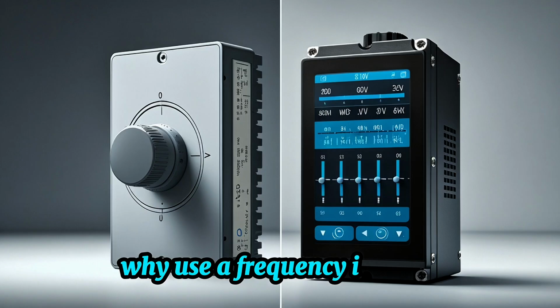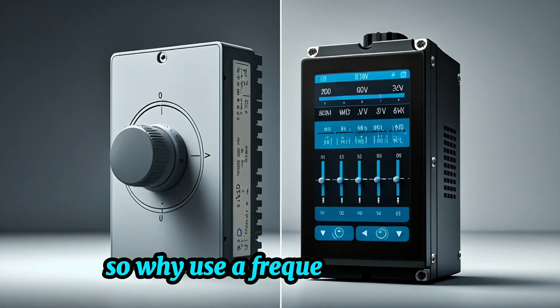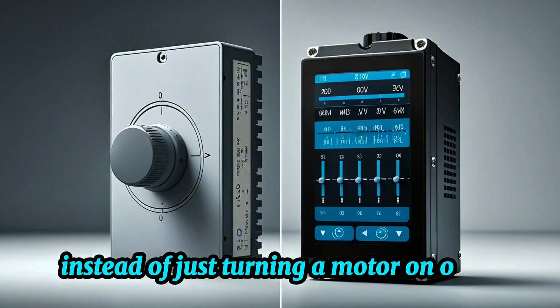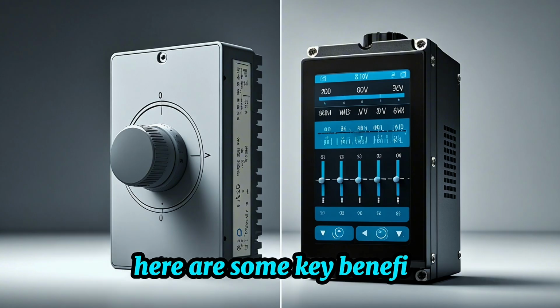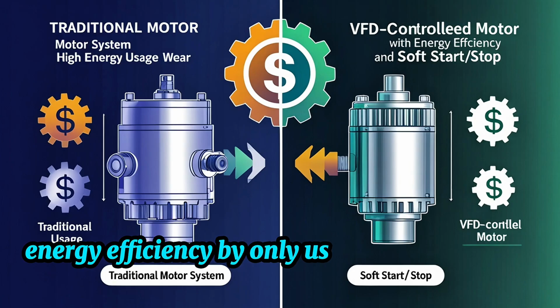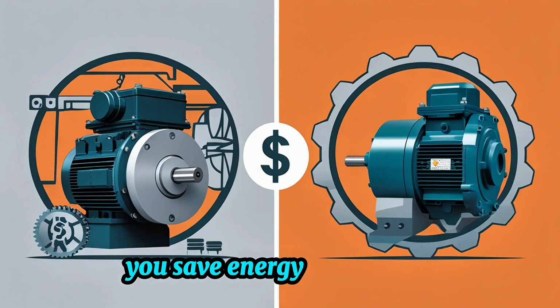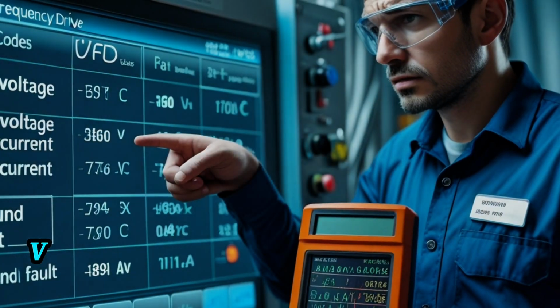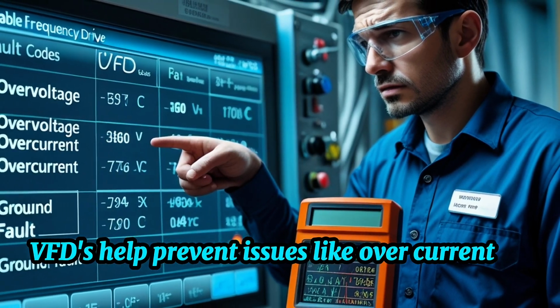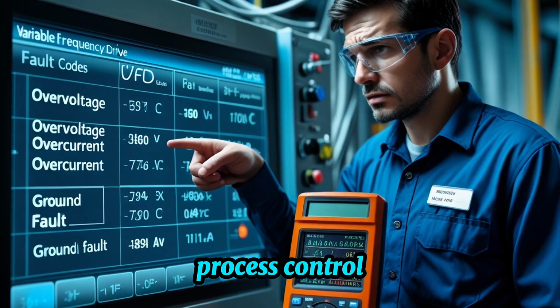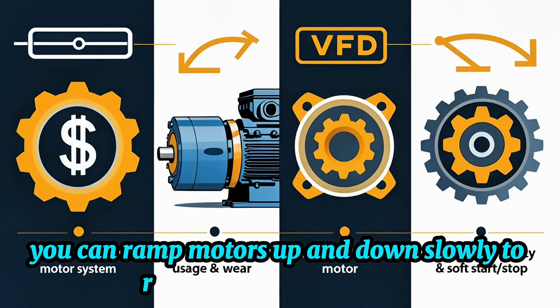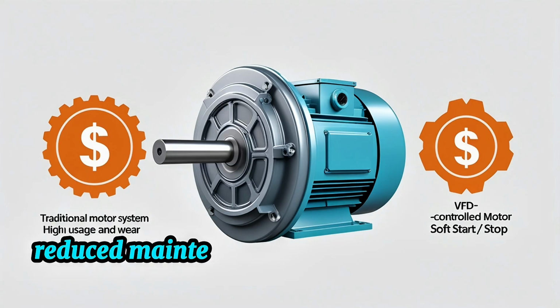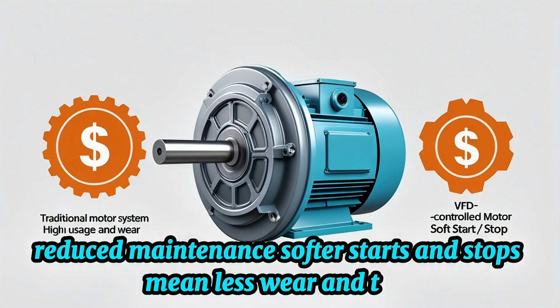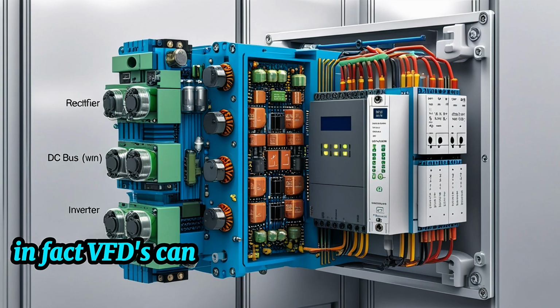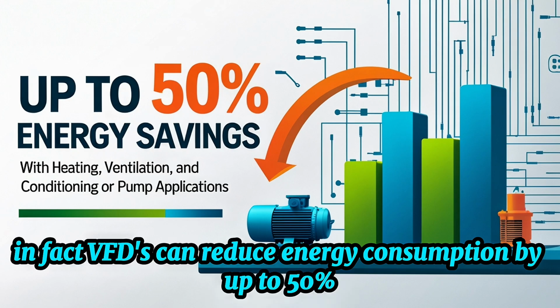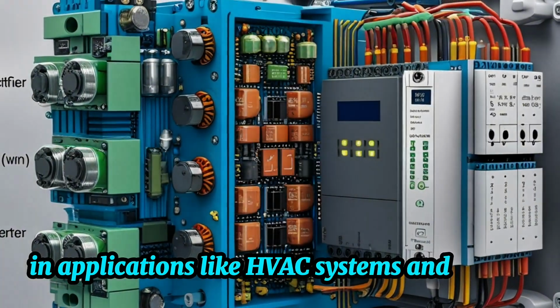Why use a frequency inverter? So, why use a frequency inverter instead of just turning a motor on or off? Here are some key benefits. Energy efficiency. By only using the power you need, you save energy and money. Motor protection. VFDs help prevent issues like overcurrent or overheating. Process control. You can ramp motors up and down slowly to reduce mechanical stress. Reduced maintenance. Softer starts and stops mean less wear and tear. In fact, VFDs can reduce energy consumption by up to 50% in applications like HVAC systems and pumps.